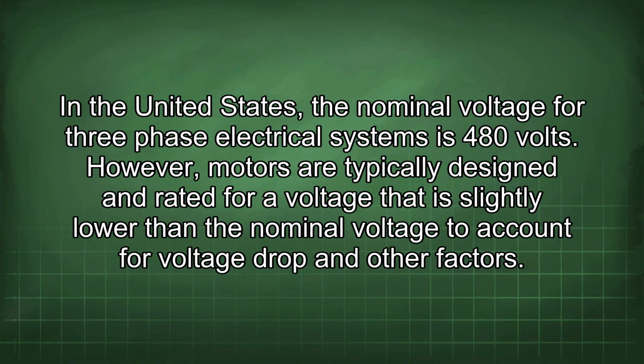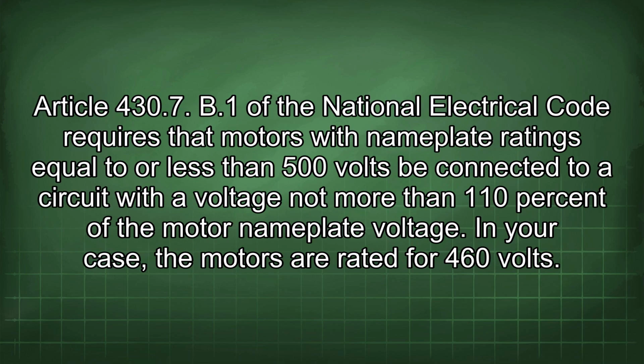United States, the nominal voltage for three-phase electrical systems is 480 volts. However, motors are typically designed and rated for a voltage that is slightly lower than the nominal voltage to account for voltage drop and other factors. Article 430.7 B1 of the National Electrical Code requires that motors with nameplate ratings equal to or less than 500 volts be connected to a circuit with a voltage not more than 110% of the motor nameplate voltage.